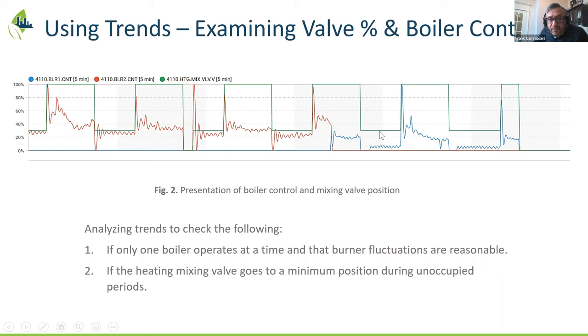And over here you can see that when boiler number two is off, boiler number one starts to kick in and it's the only one operating. Its burner fluctuations are reasonable - not crazy, not cycling throughout this whole graph. So again, this shows further evidence of how you use trends and the importance of confirming your equipment is actually working as intended.